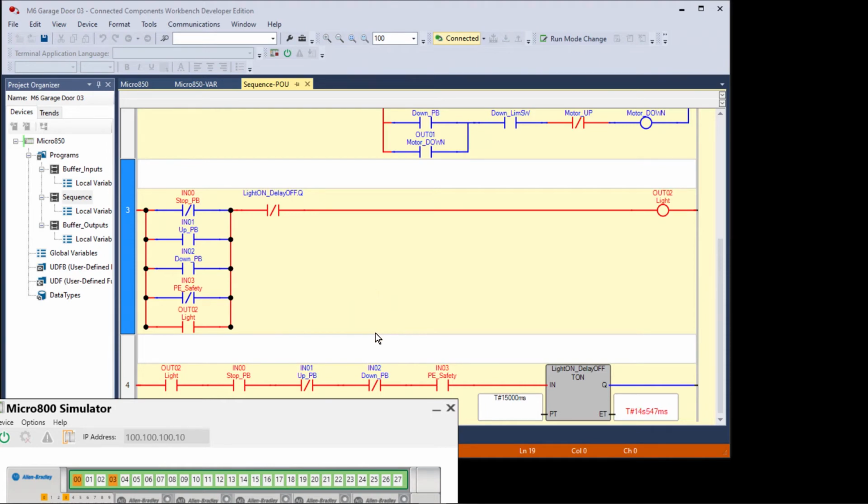Well, you might be looking at a wraparound, a folded, a big fat long rung, and you can't see the whole rung on the screen. But if you see that little blue piece before a true instruction, you know that the state in from somewhere earlier in the rung is false. There's the culprit right there.